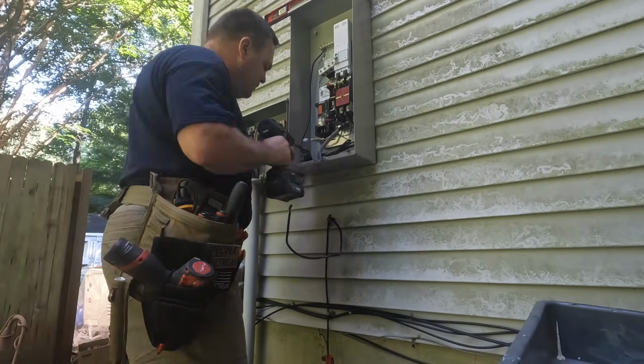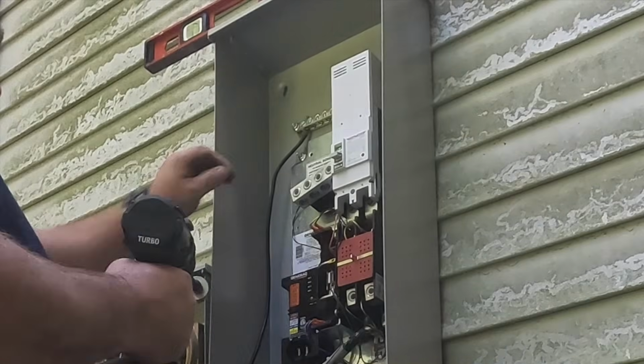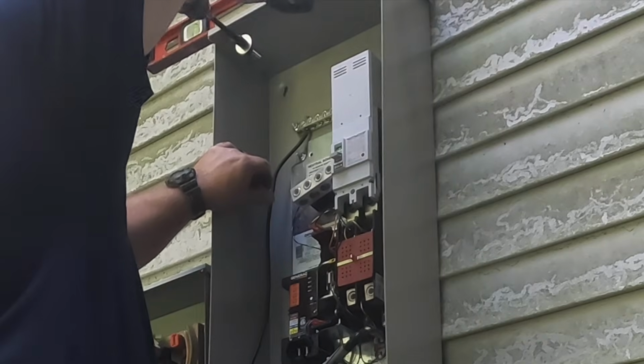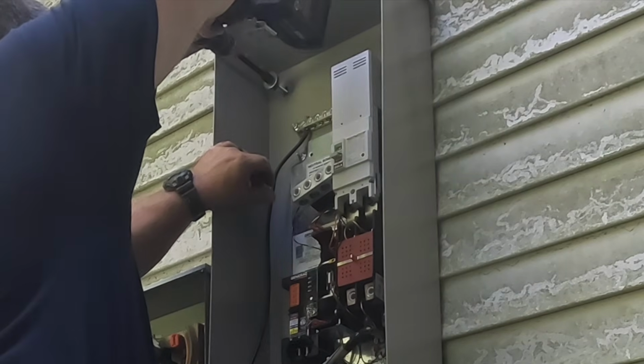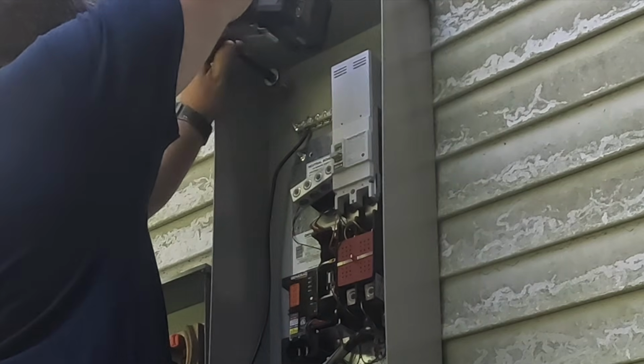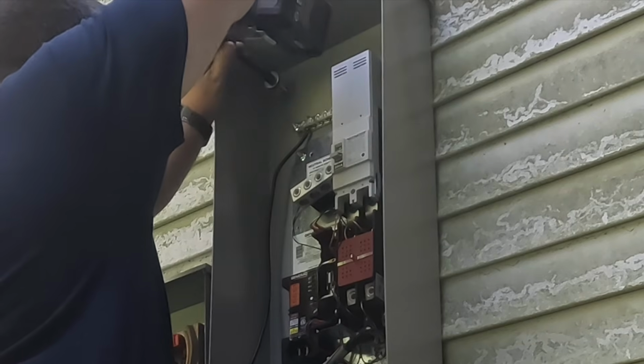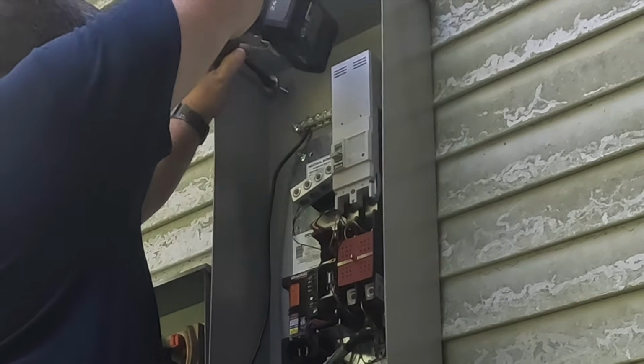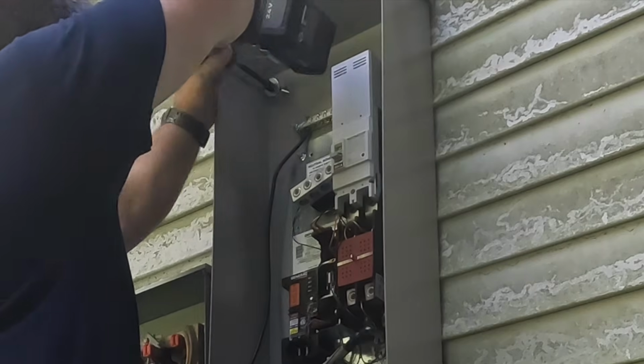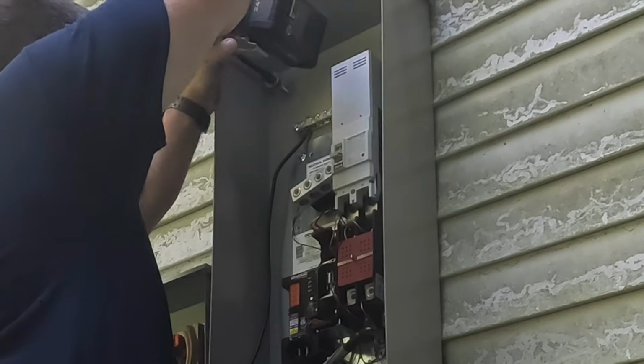Now also keep in mind that this transfer switch's enclosure is made out of aluminum, so you cannot use the magnetic properties of a box level to make sure that this is straight. So I got to use it on the top and of course on the bottom as well to make sure that it's level.